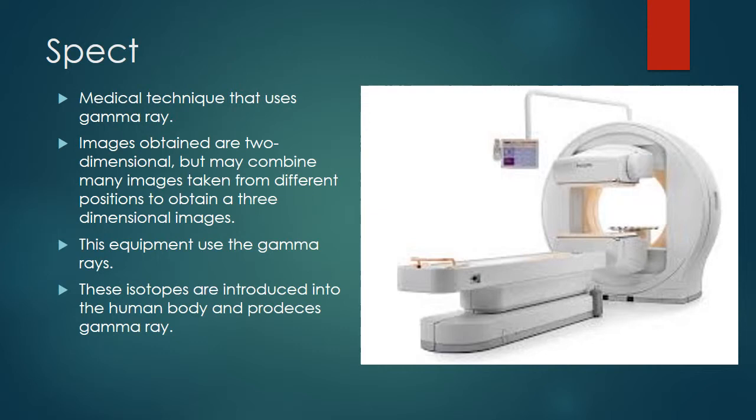The gamma camera is rotated around the patient. Images at different angles are acquired, typically every 3 to 6 degrees. In most cases, a full 360-degree rotation is performed, allowing the reconstruction of images in 3D. Each image typically takes 15 to 20 seconds, so the whole process takes about 15 to 20 minutes.